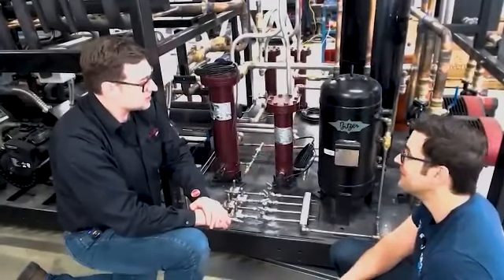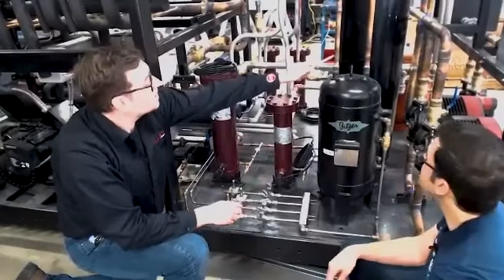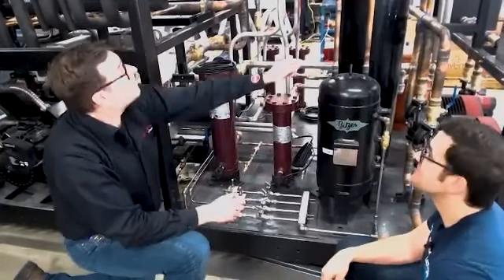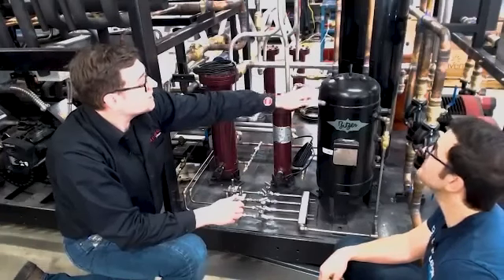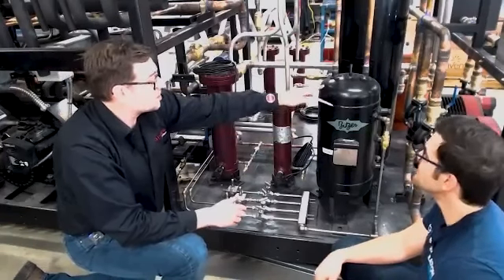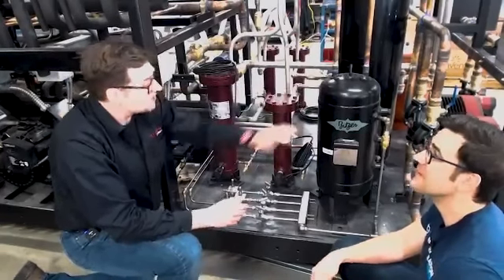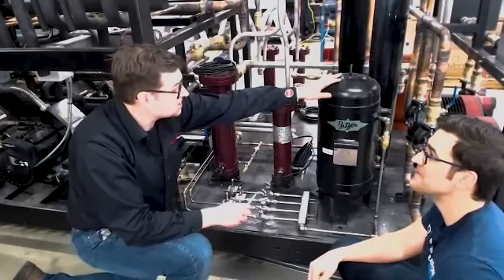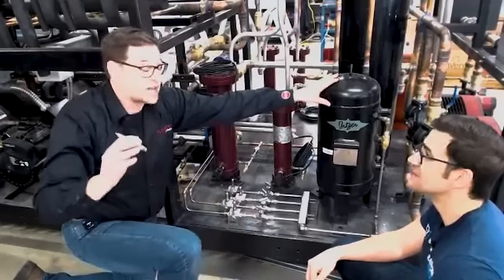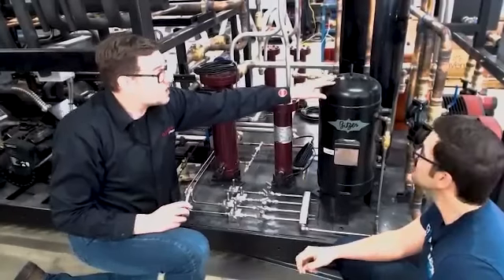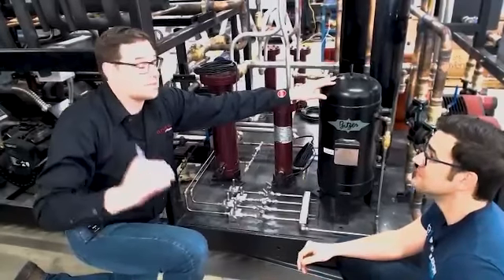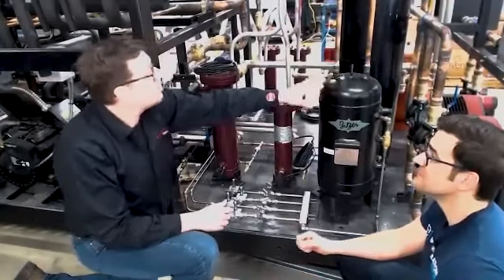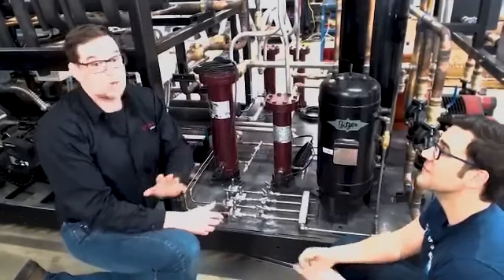This is key - we get asked quite often how this is depressurizing. There's nothing you should really be concerned of, it's going to do it naturally. But with any system that depressurizes in the flash tank, remember when we spoke about flash tank management, we have to be conscientious as we change flash tank pressure, because we could offset how our other components within the system are working.